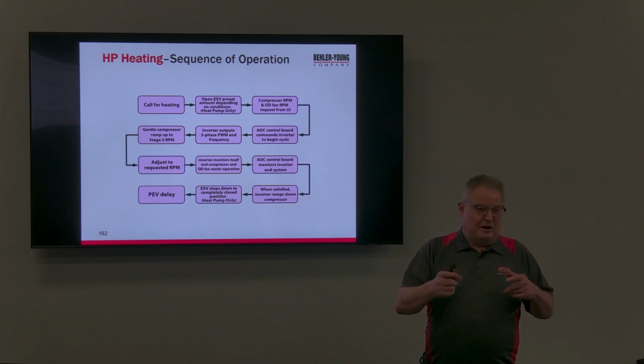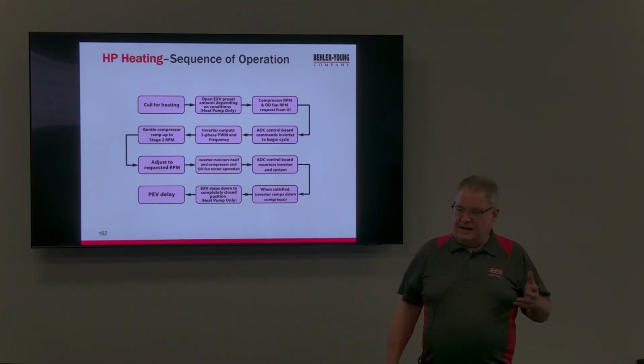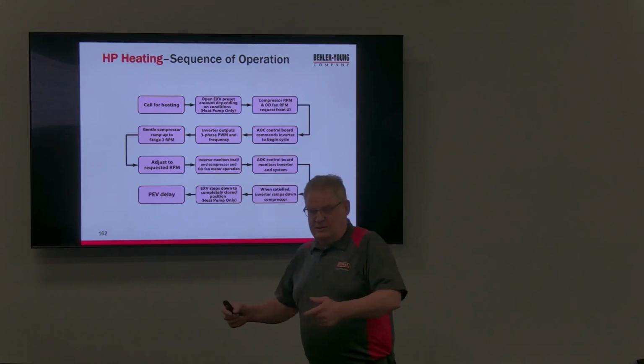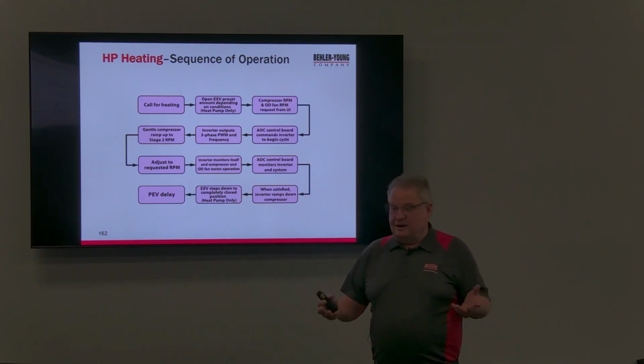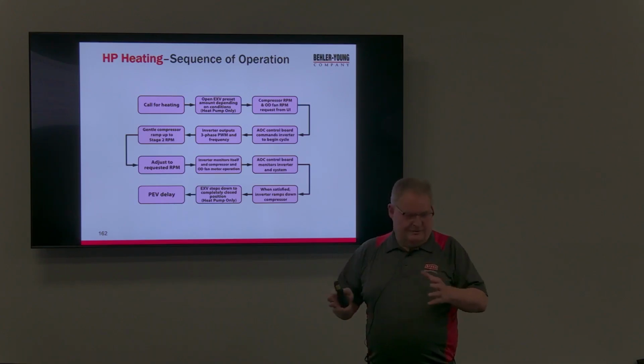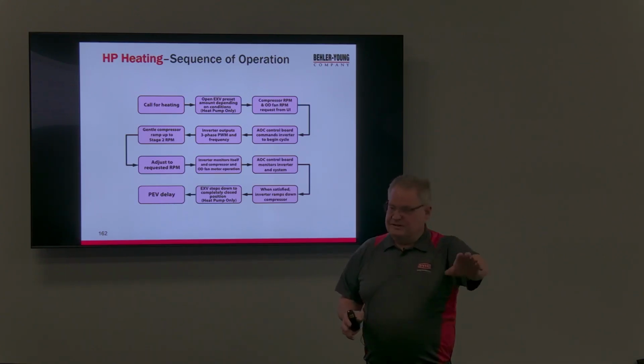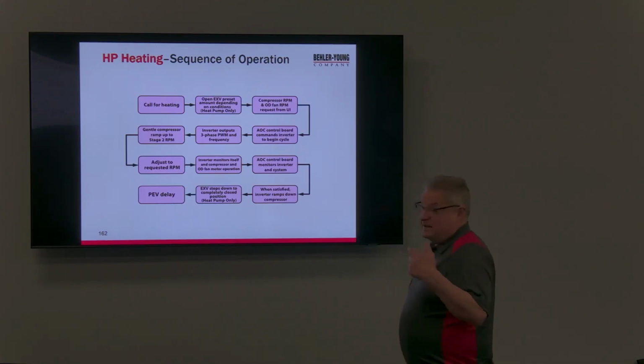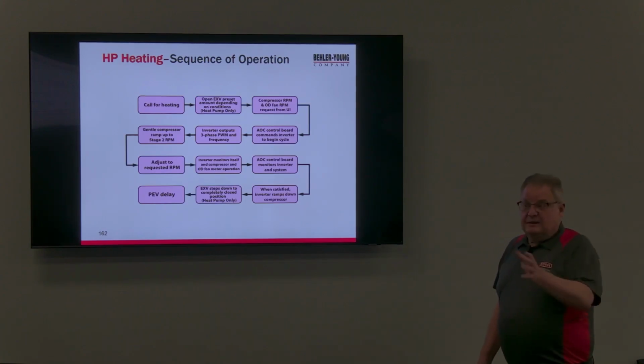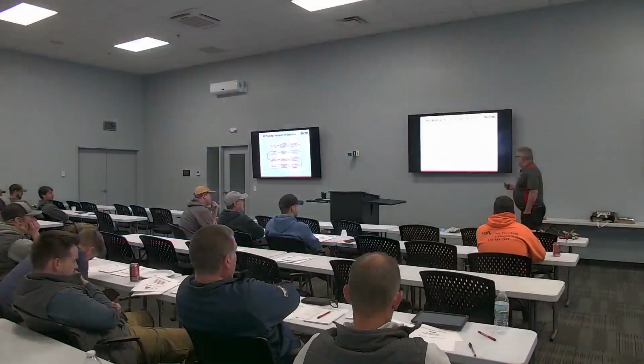And it gets kind of weird if you haven't done too many heat pumps and you're going off on high head pressure in heating and you're out checking your condenser fan, your condenser coil. Wait a minute here. Might be a dirty air filter. It's still sometimes hard to wrap your brain around. It's like, wait a minute. Well, no, that's not the evaporator. Now that's the condenser. So airflow is a big thing on the heating side when we're running a heat pump as well.